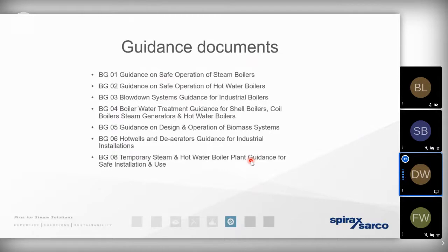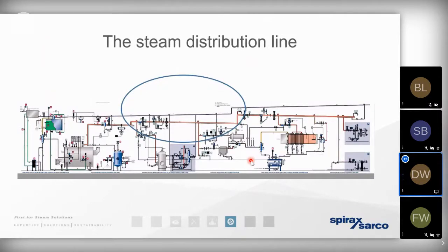If you want to improve the overall efficiency of steam generation, if you want to ensure that you get a consistently good condition of steam being produced, then we do need to move to a more sophisticated series of controls. Even when we are generating an excellent condition of steam, with the best controls and the best water quality, it all means nothing if we're not observing good working practice in how we convey that steam from the point of generation to the point of use. That's why it's important to give thought to those basic design considerations.